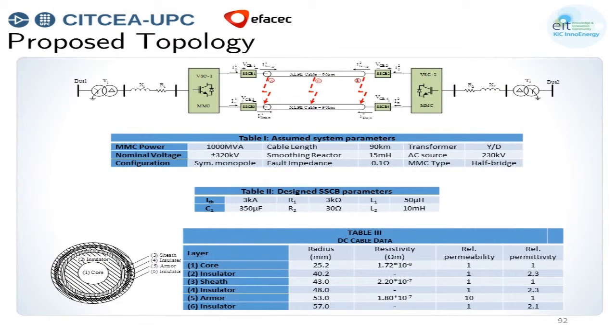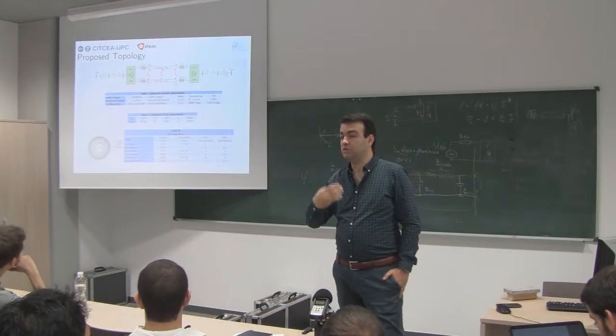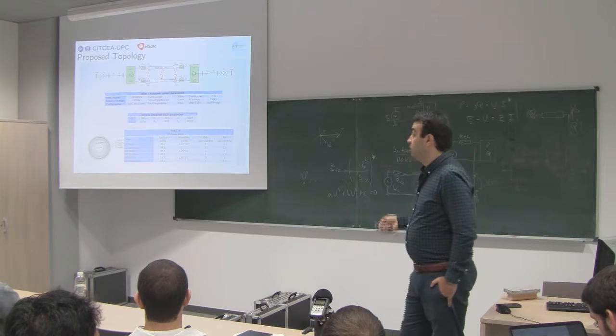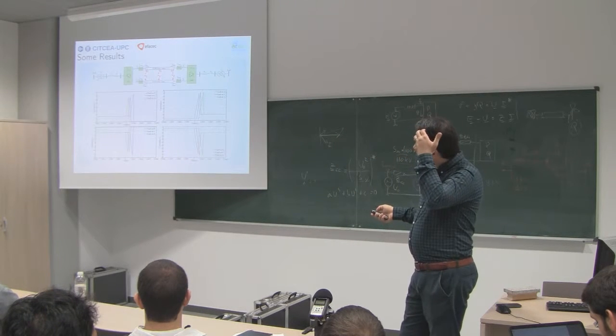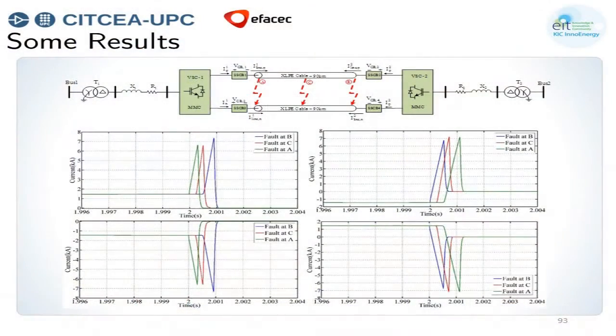So just to show you how it works, I have a model here, which is modeled mainly in PSCAD. We use the frequency-dependent model of the cable. We implemented the model from these physical dimensions that we have here. The voltage rating is plus minus 320 kV, and the configuration is a symmetric monopole configuration of HVDC. So we can integrate the same circuit breaker into any kind of HVDC configuration, like asymmetric and symmetric monopoles or bipolar configuration.